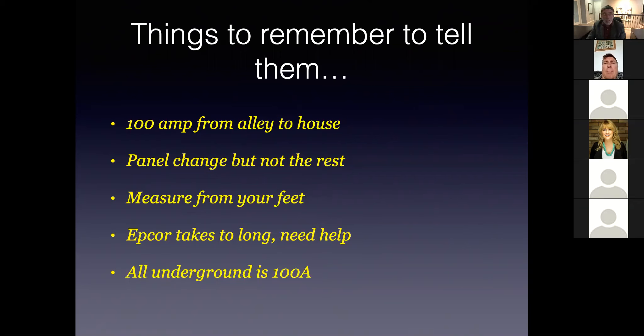The height requirement for a meter is five foot to five foot six. If you're going over different aspects of the house with your client and you notice a deck was built, the standard meter would now be about two feet off the deck. But where you measure from is your feet. If you walk up the stairs to the deck, stand on the deck, and look down and there's a glass meter — that's something you can bring to their attention, because the home inspector, who I've also trained, is going to know about this and bring it up as a deficiency.